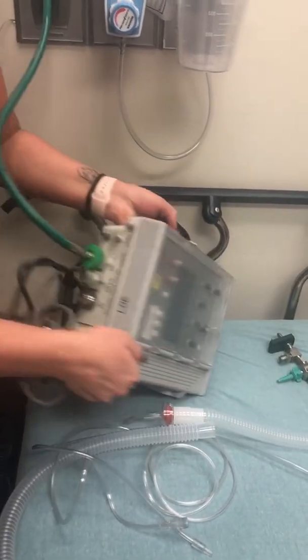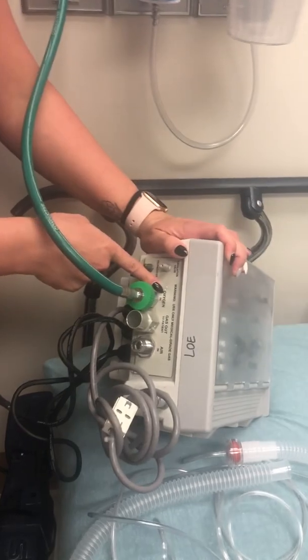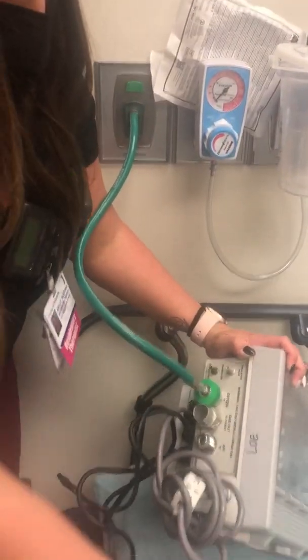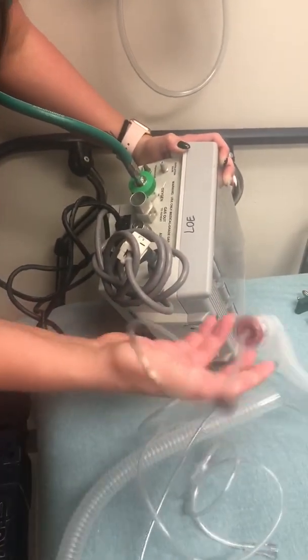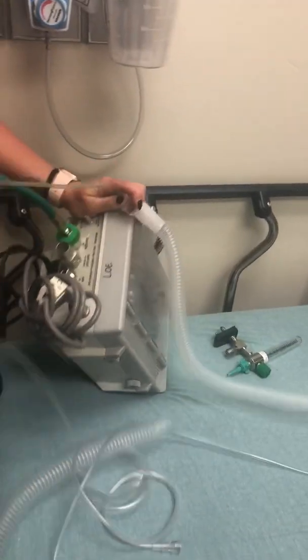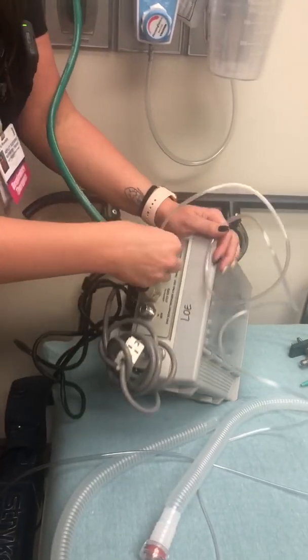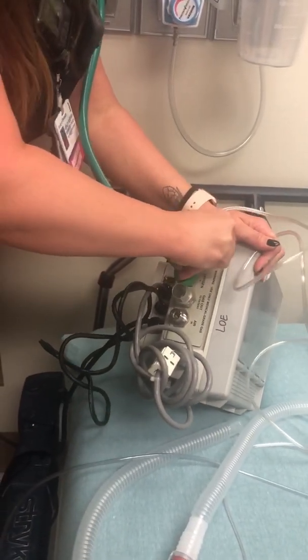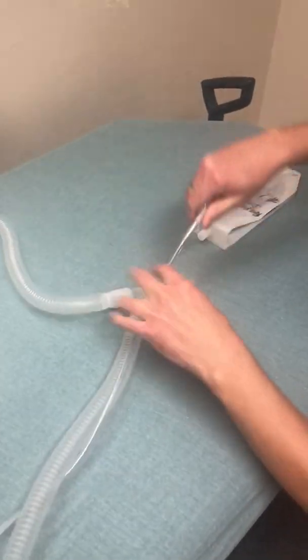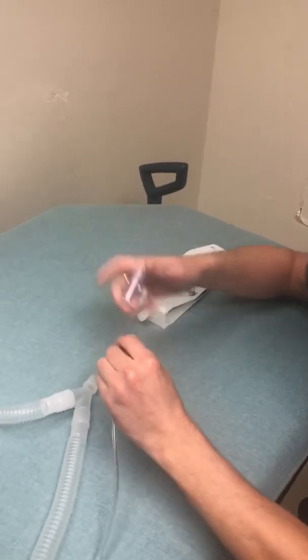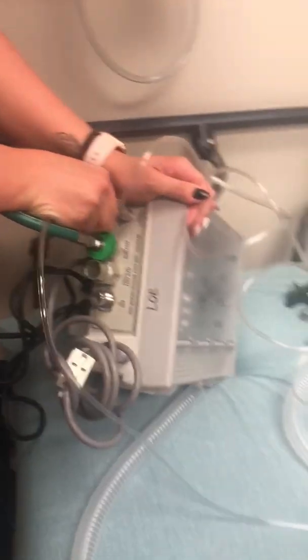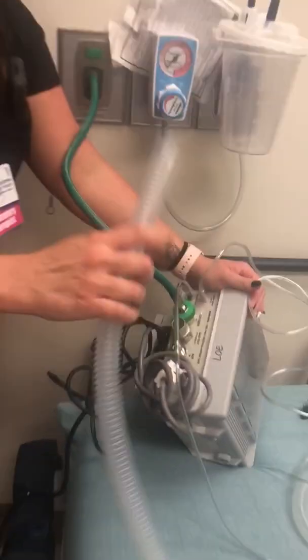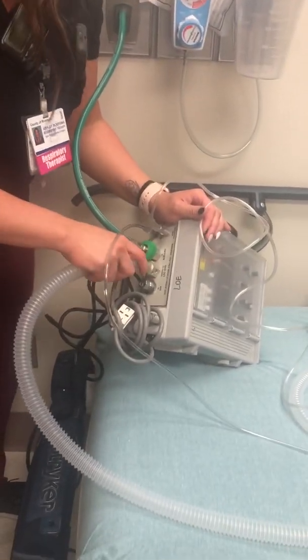So here on the side of the ventilator is the oxygen. You just feed it here. Then you have your exhalation valve, and that's this red piece. You connect that to the exhalation port. And then the transducer is fed from the top. Wonderful. So you connect that there, and that's on your transducer. Then this is to the patient, and this is going to go on your gas out to the patient. Okay.